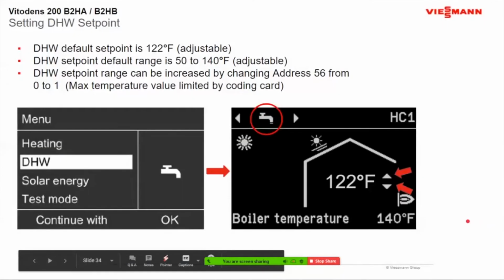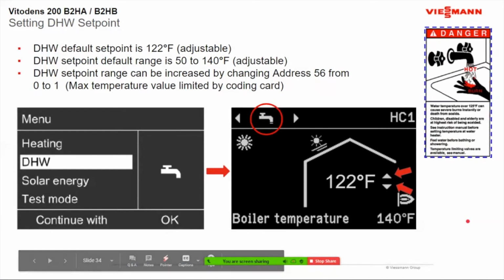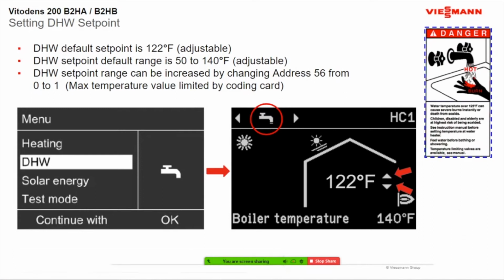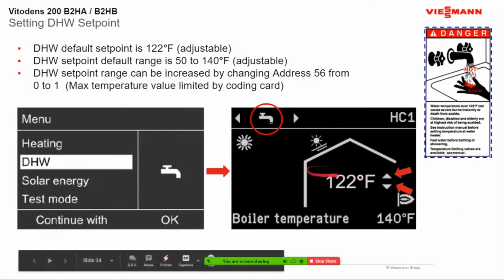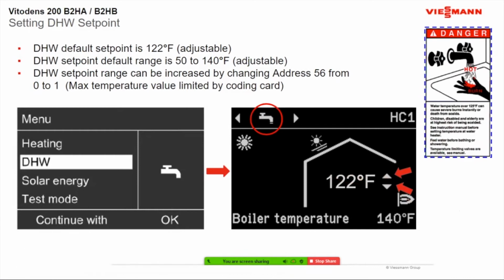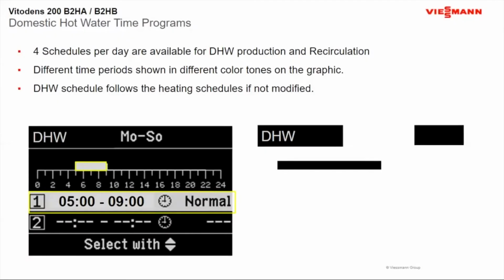So once we click on that, it'll allow you to adjust your domestic set point. It'll come up on the screen. If you're doing zone circuits, it'll be a little different. But you'll just go up and down with your up and down arrow to adjust your temperature here. If you're going above, I think it's 118 here in Massachusetts, an anti-scald valve is recommended, or code actually. And if you're doing your domestic, this is just showing you what the screen would look like for your domestic time program or recirculation program.